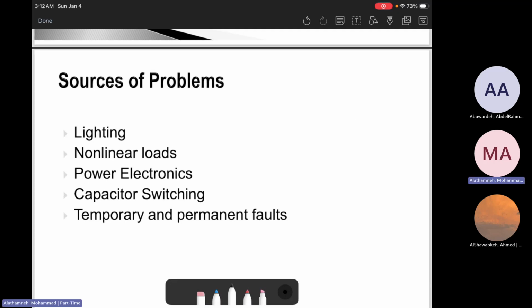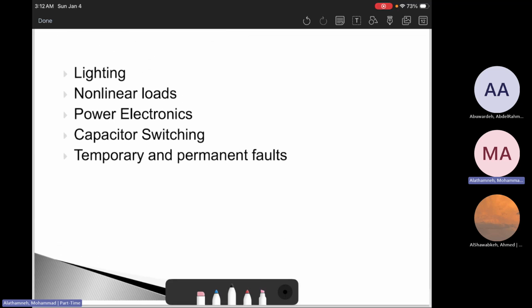Okay, so the sources of the problems are basically lightning, nonlinear loads, power electronics, capacitor switching, temporary and permanent faults. These are the sources. Then we need to make sure the power quality events are electromagnetic phenomena. That means we need to describe them using magnitude, duration, frequency content, repetition rates, and energy. This is exactly why monitoring standards like IEEE 1159 focus on consistent description of conducted electromagnetic phenomena.